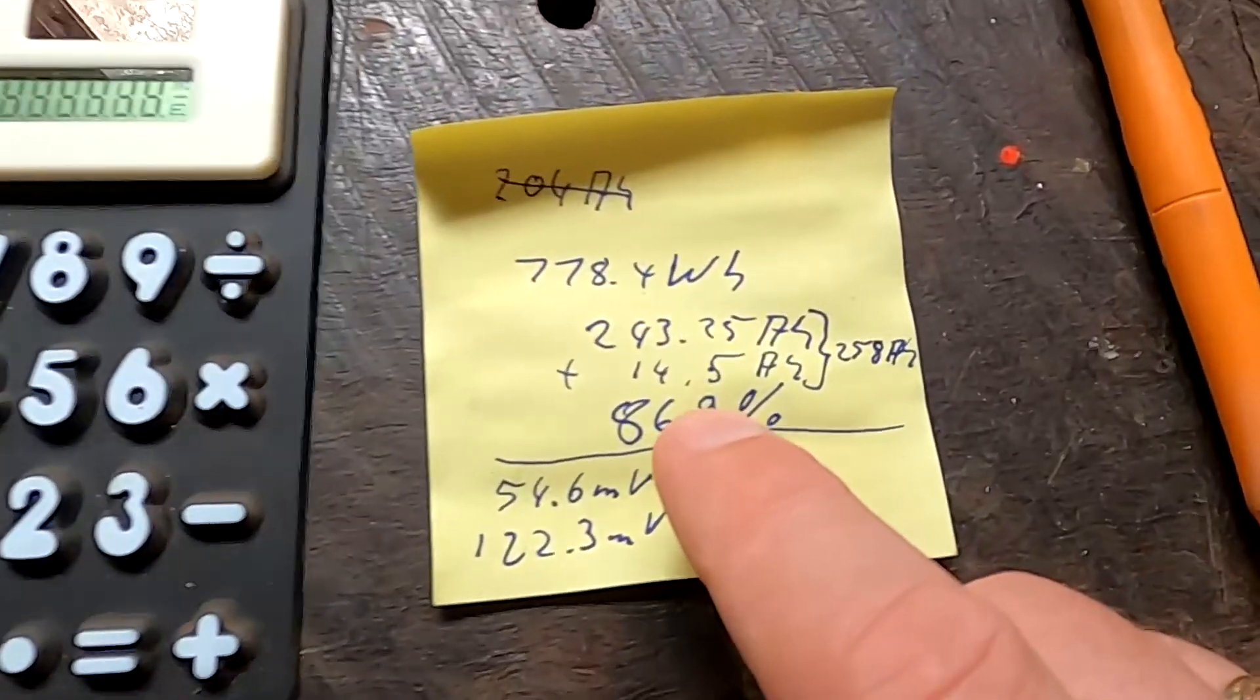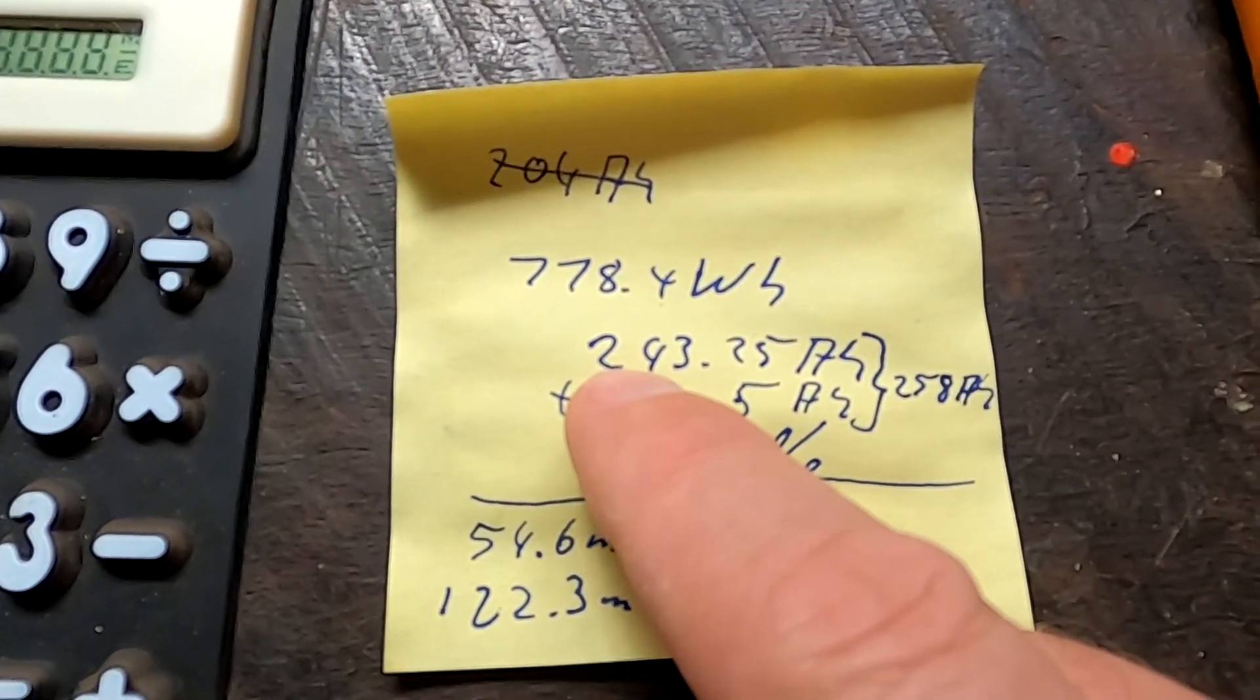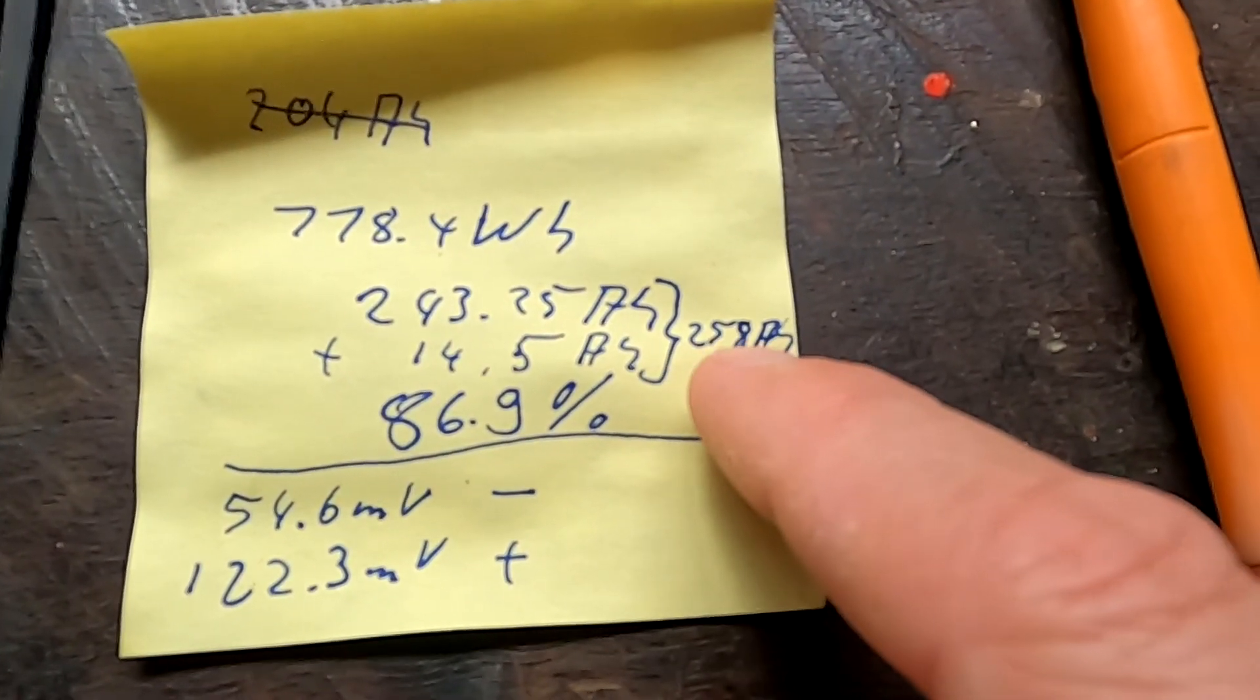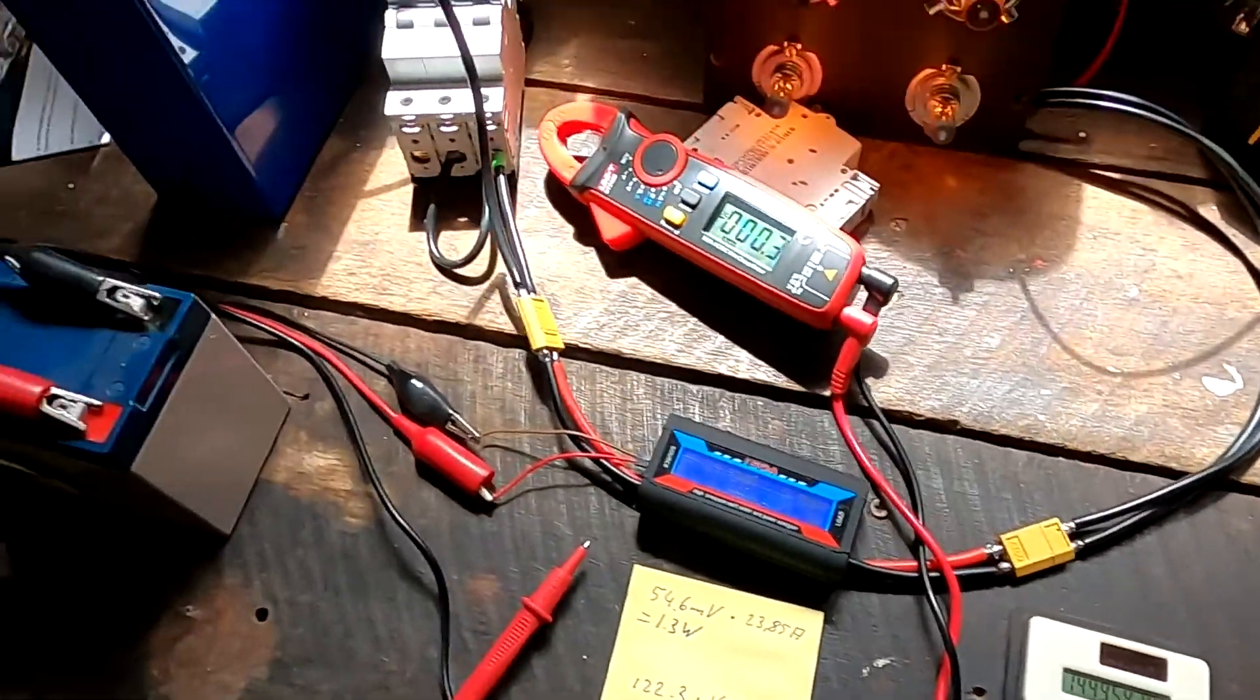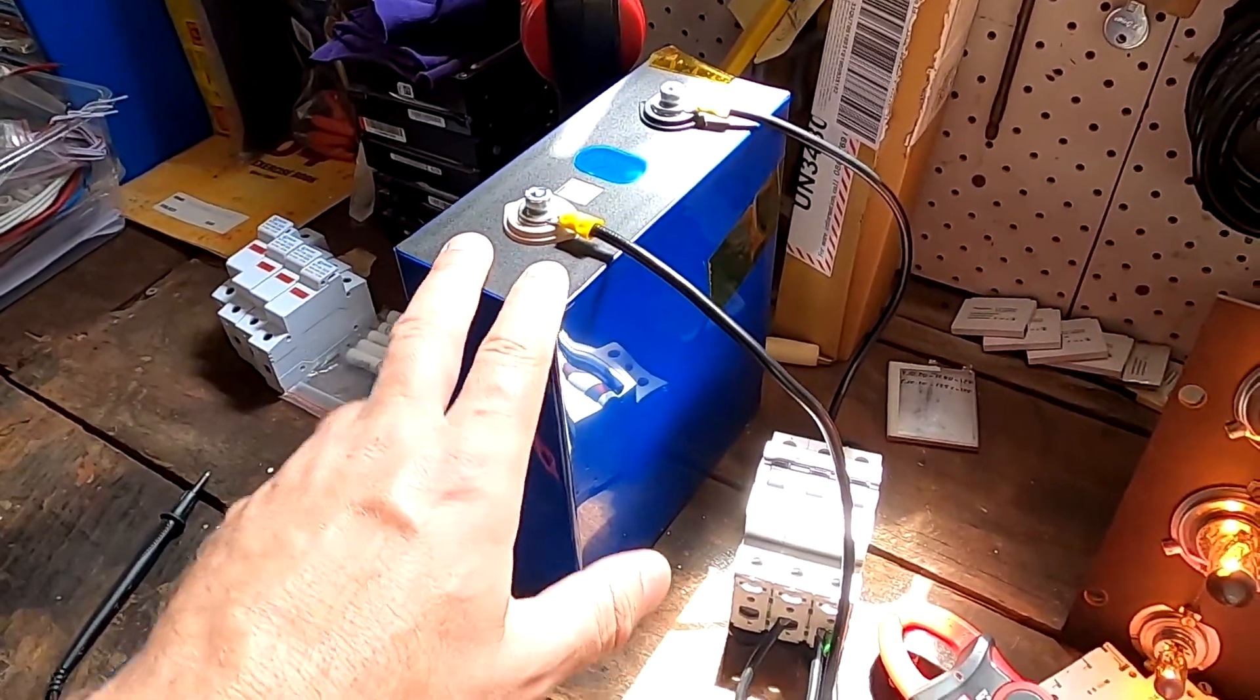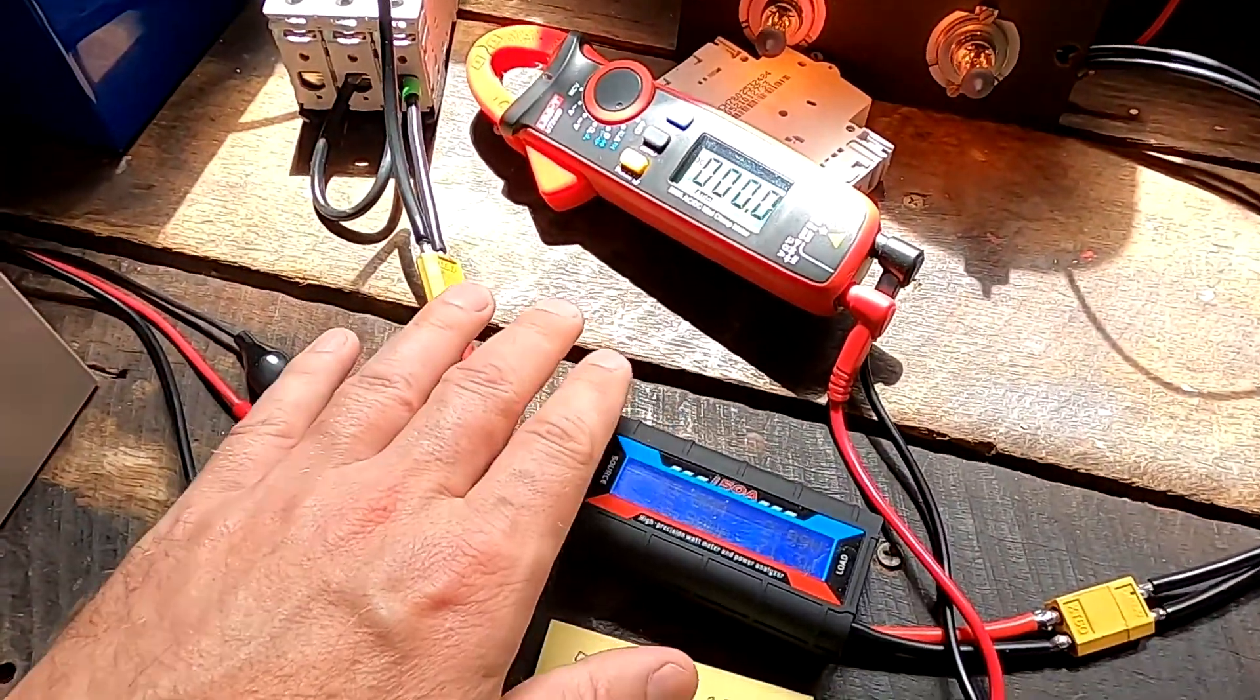I'm adding these 14.5 ampere hours to our measured 243 ampere hours and we get 258 ampere hours out of the battery. This is what we discharged from the battery - we lost about 14.5 ampere hours on our setup before reaching the meter.